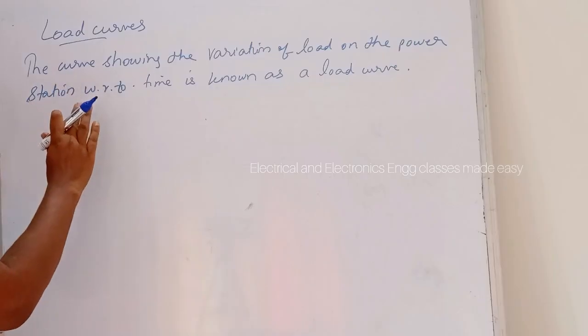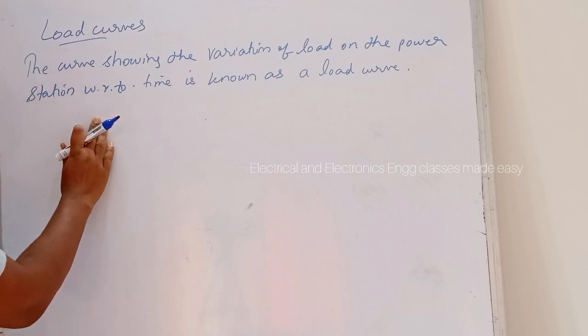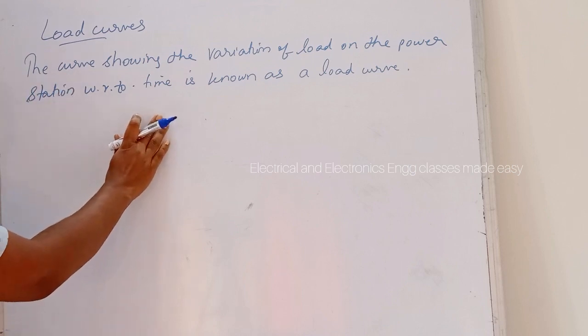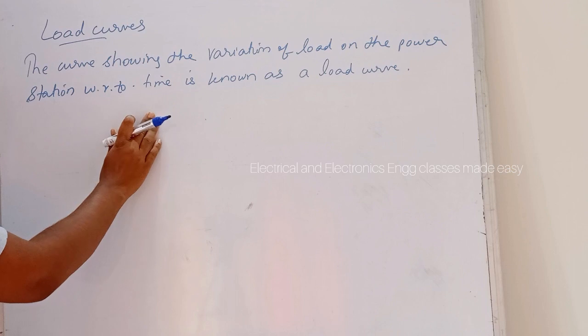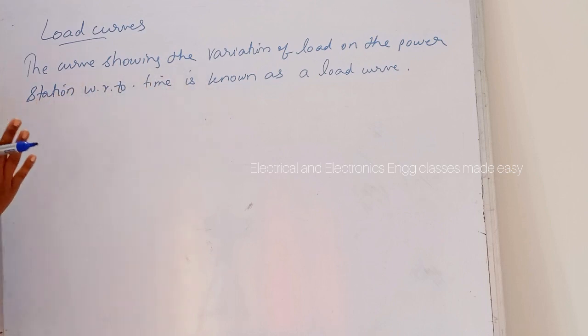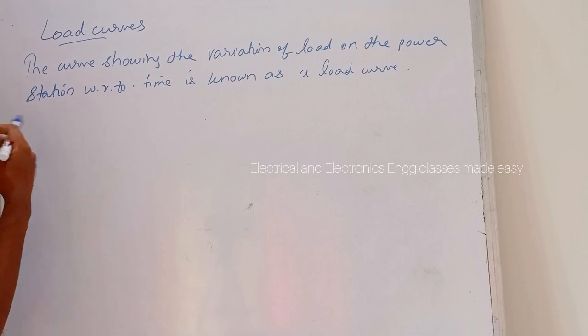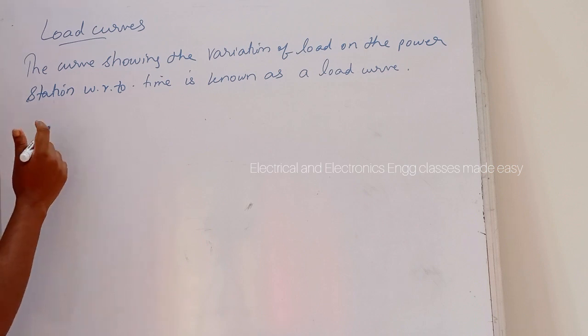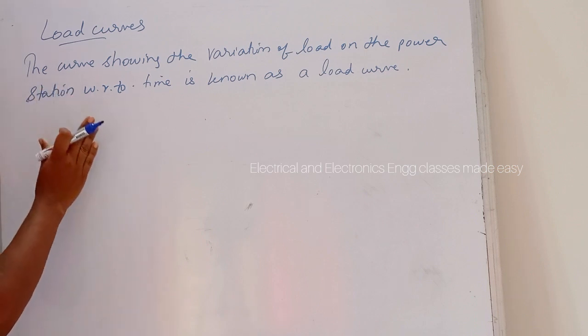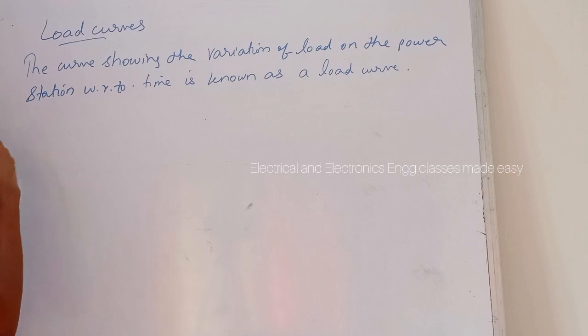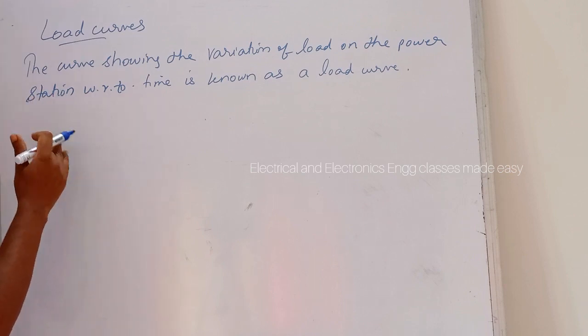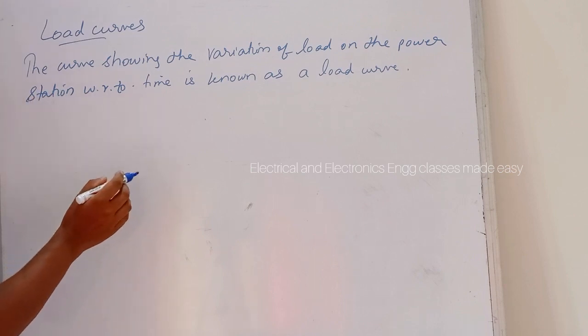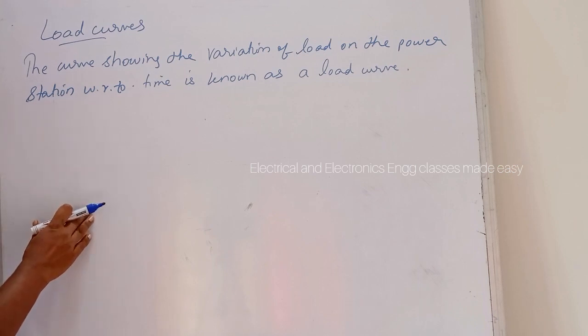Next is load curves. The curve showing the variation of load on the power station with respect to time is known as a load curve. The load on a power station is never constant. It varies from time to time. And these load variations during the whole day are recorded half hourly or hourly and are plotted against time on the graph.